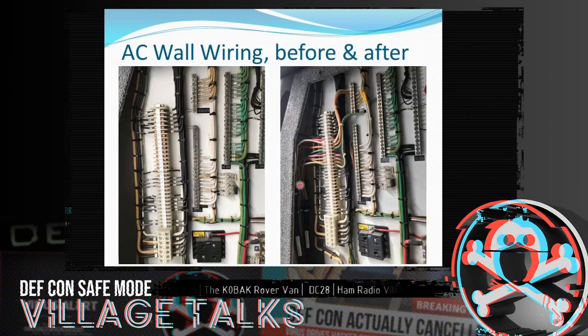This is a before picture and this is an after picture, and you can see those same two multi-wire cables coming up into the panel on this side and being wired into existing circuits. You can see that I was lucky that this terminal block had a lot of unused circuits, so that made it a lot easier than it would otherwise have been to wire in my own connections into the AC panel.